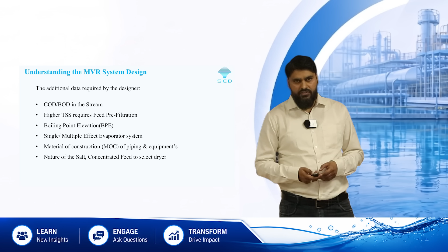Evaporators are used where larger volumes need to be evaporated. This can be single or multiple effect evaporators, and forced circulation depending on higher TDS. If the TDS becomes higher and higher, we use forced circulation evaporators.